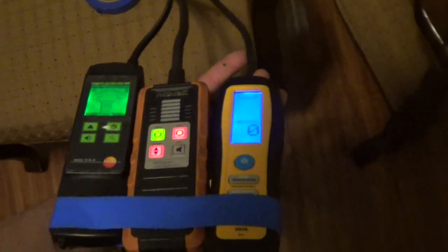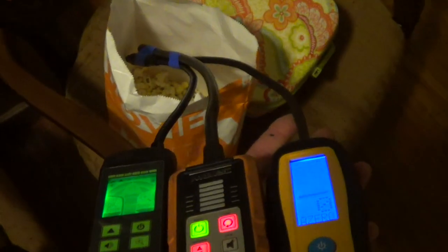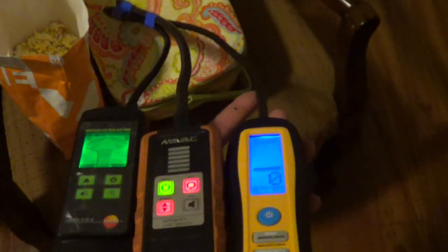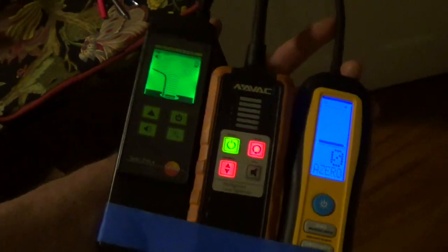Let's check this tape — see if the tape has a Freon leak. Let's check this chair, see if there are any Freon leaks on that. Let's check this bag of movie popcorn, see if we've got any Freon leaks in there. Sewing box. The Navac's going off. I've been using the Navac in the field for a couple of years. This one has a new sensor — it's more stable than the SRL-8. Let's see if we've got any leaks on this doorknob. The Navac is giving a nuisance trip.